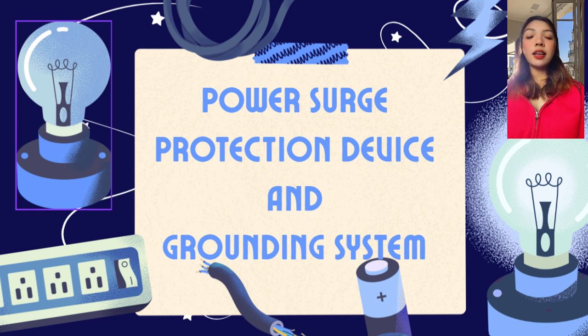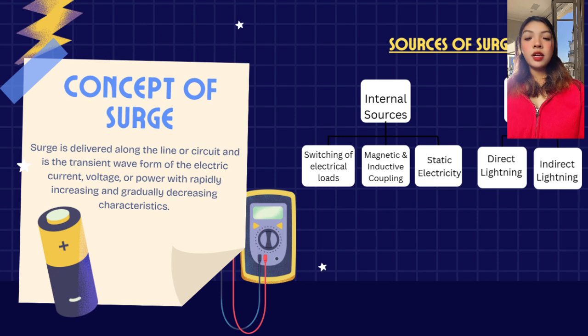The next is the concept of surge. A surge is a sudden and temporary increase in voltage, current, or power in an electrical circuit. It has a rapid rise and gradual fall. It is also called a transient waveform. A surge is like a spike of electricity that appears quickly and disappears after a short time but can cause serious damage. There are sources of surge that come from two main categories.